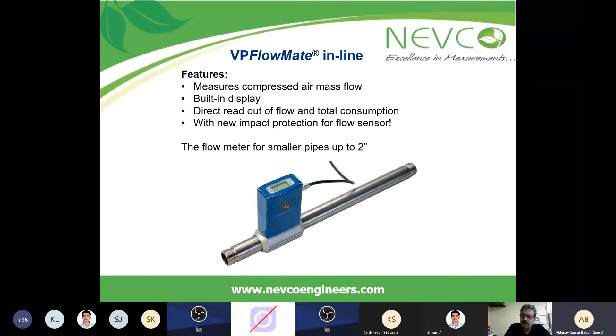So we have a model called VPFlowMate, an inline model, and we also have a portable model - a 3-in-1 device that can measure flow, pressure, and temperature with a built-in data logger, and it can also audit. It can see the exact compressed air delivery to a particular machine or application, because compressed air is money - a lot of money is spent on it. So these instruments are available to measure pressure and flow, and accordingly you can decide exactly where the pressure is dropping or where there is a leak.